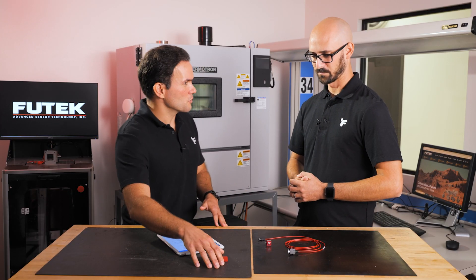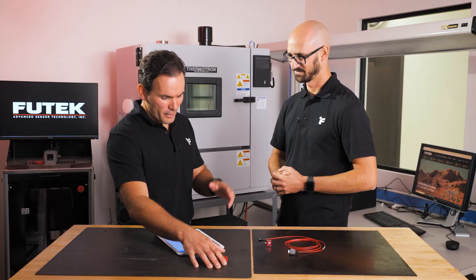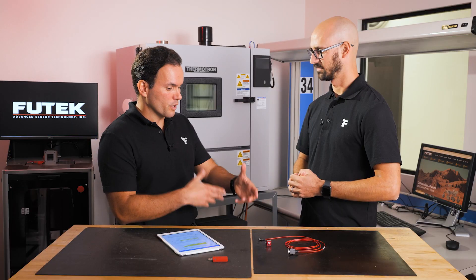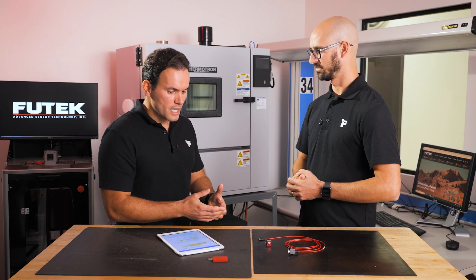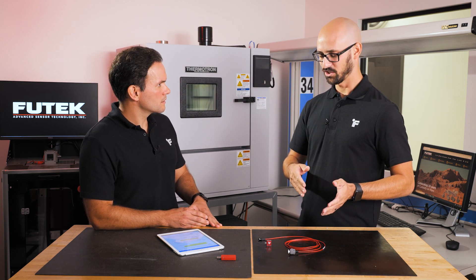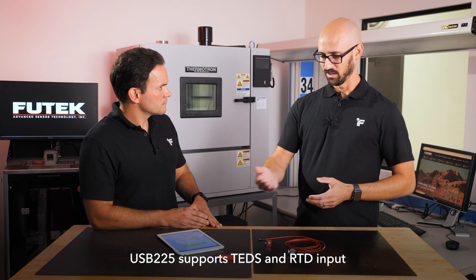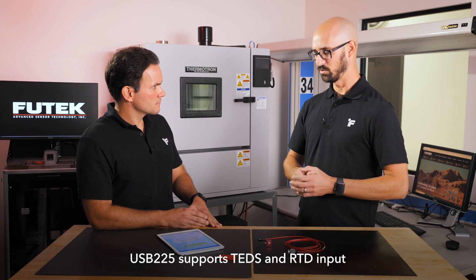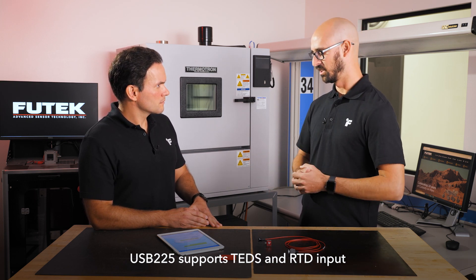You keep mentioning the signal conditioner. For the PT1000 and TEDS chip — all those embedded features and functionalities of the LSB205 — you also need a compatible signal conditioner for them to work properly. You don't necessarily need it, but it's very helpful because it takes care of all the guesswork on the initial setup. The USB225 can take the PT1000 RTD input and the TEDS input, and use that information to handle compensation and calibration in one device rather than configuring everything on the user end.